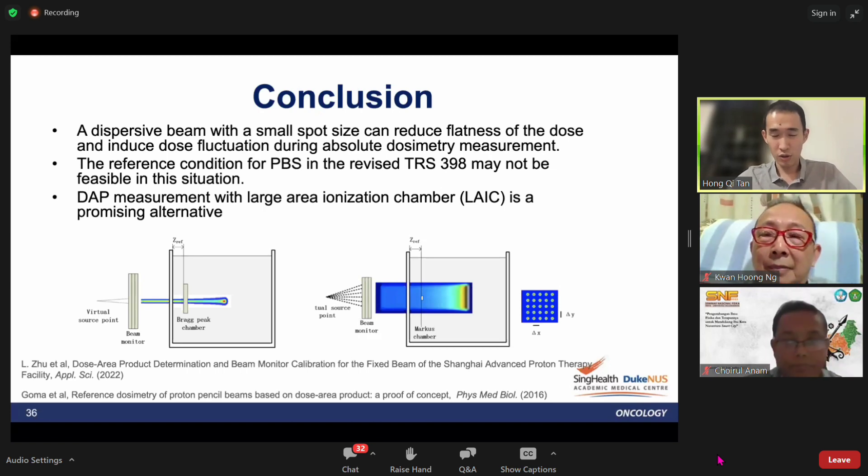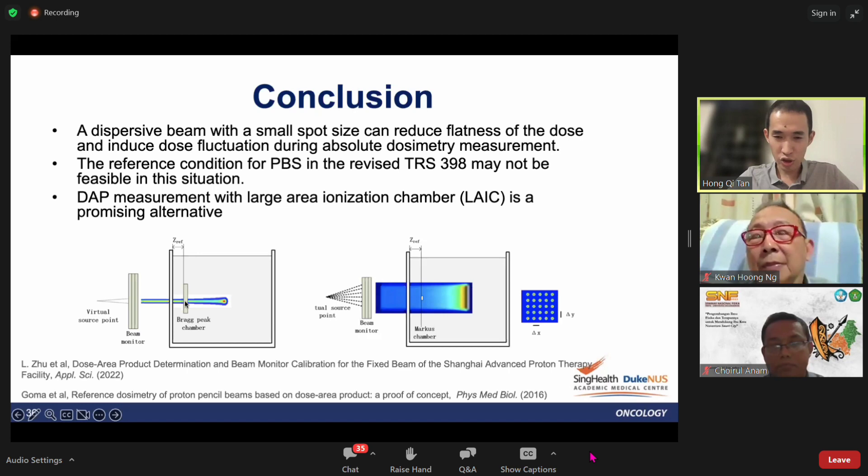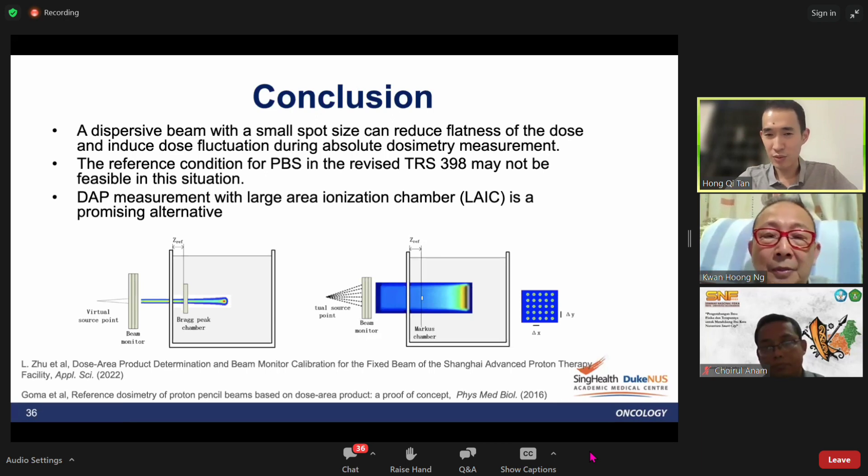Several research groups show that it's possible to do dose area product measurements using large area ionization chambers. There's a couple of work out there, and as shown here, ideally you need reciprocity conditions. These two conditions should give very similar DAP measurements. With a practical chamber with a single spot, the good thing is it's insensitive to any spot positional drift. We think this will be a promising step forward to overcome this problem.